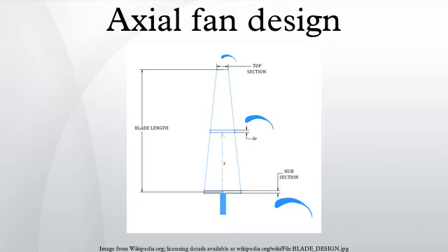Paralleling: this effect is seen only in the case of multiple fans. The airflow capacities of the fans are compared and connected to the same outlet or same inlet conditions. This causes noise, specifically referred to as beating in the case of fans in parallel. To avoid beating, use is made of differing inlet conditions, differences in rotational speeds of the fans, etc.